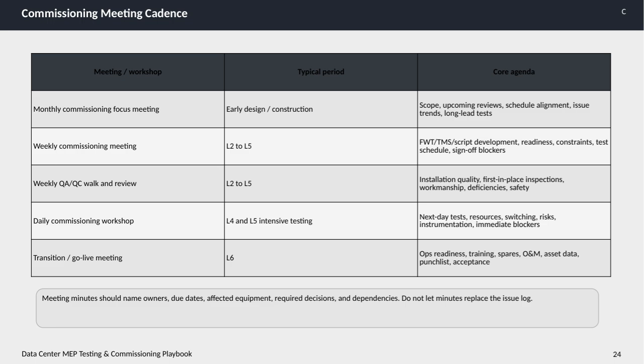These focus on functional and integrated testing development, readiness checks, constraints, test scheduling, and identifying any blockers to sign off. Alongside, we have the weekly QA/QC walk and review, also from Level 2 to Level 5, concentrating on installation quality, first in-place inspections, workmanship, any deficiencies found, and safety concerns. During the intensive testing phases at Levels 4 and 5, daily commissioning workshops are held. These focus on planning next-day tests, resource management, switching operations, risk management, instrumentation, and addressing any immediate blockers that arise.